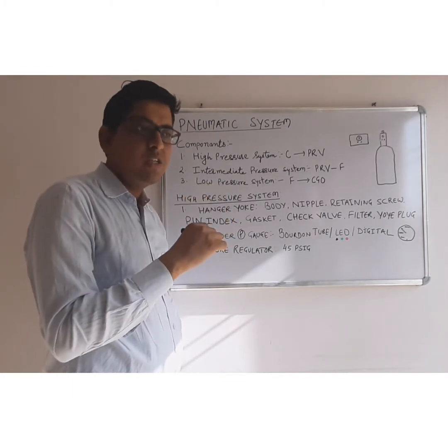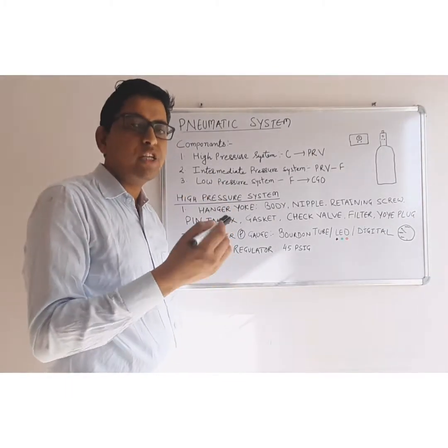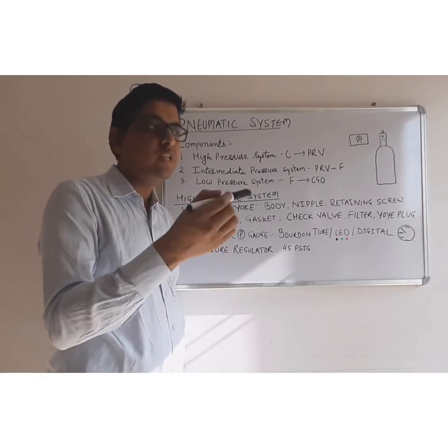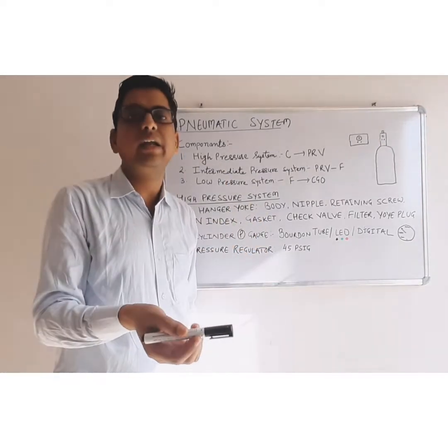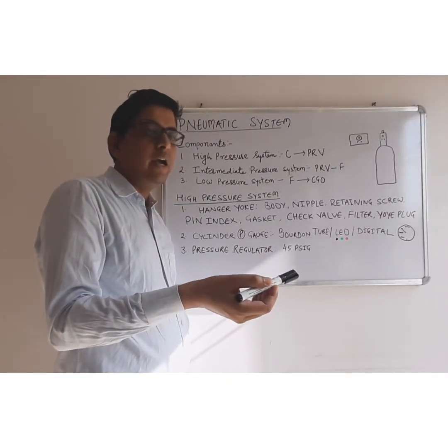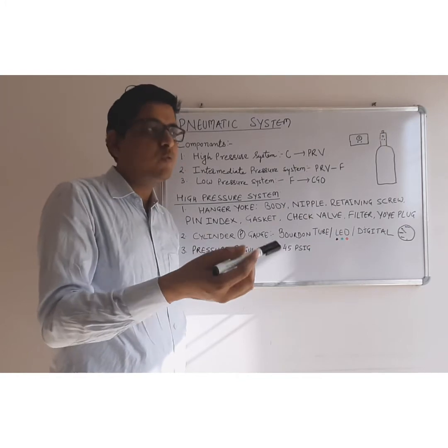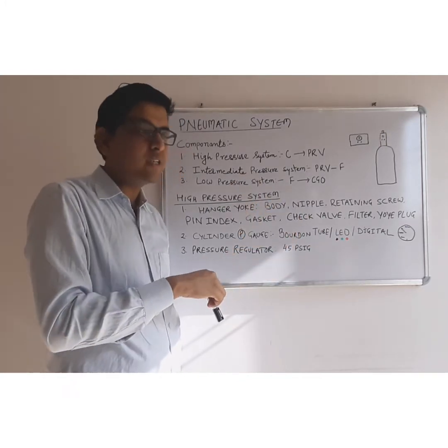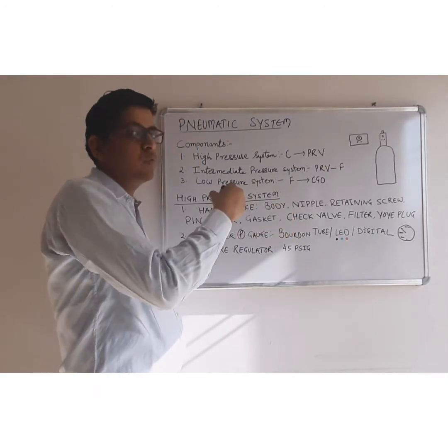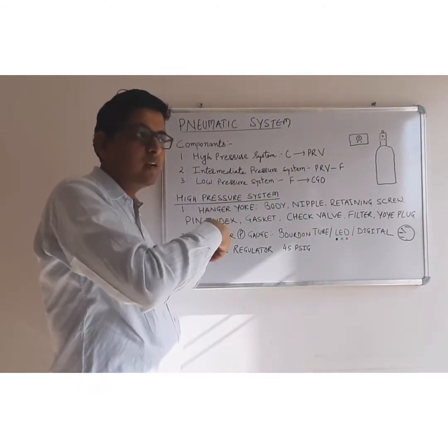In some machines there is provision of attachment of 2 cylinders, and both the cylinders are open and one cylinder is full while the other cylinder is empty. So there will be entry of gas from the full cylinder to the empty cylinder. So this unidirectional valve will prevent this transfilling from one cylinder to another cylinder.